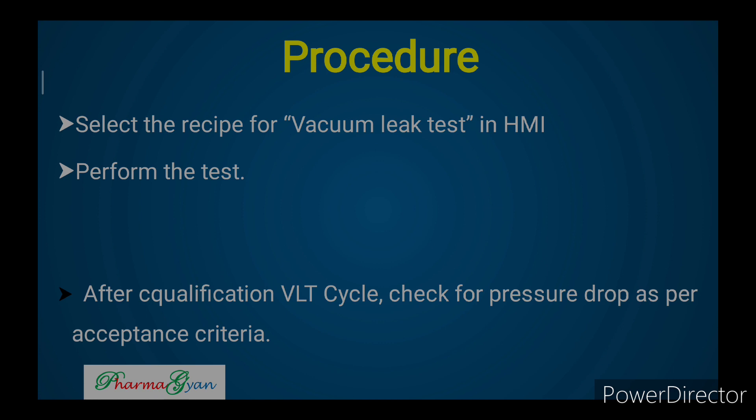The procedure is simple: close the chamber door and from the HMI, select the vacuum leak test recipe that you have developed, then run it. Once you run it, the vacuum leak test will automatically start in the autoclave. When the cycle is complete, verify from the printout how much air leakage was detected.